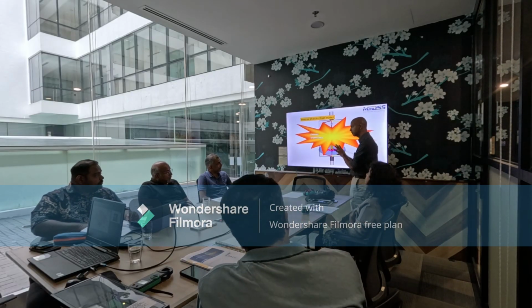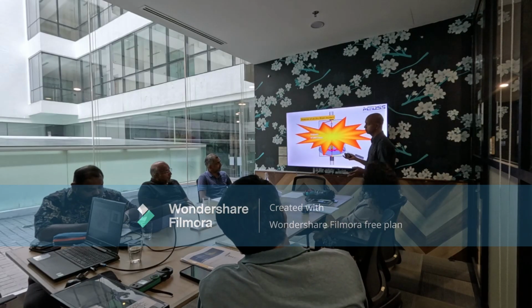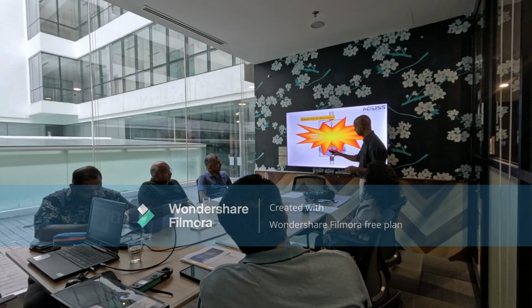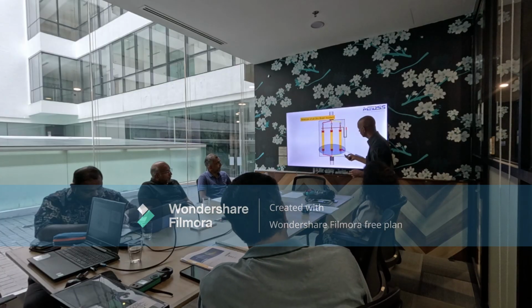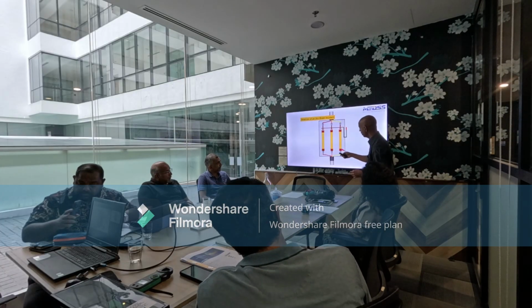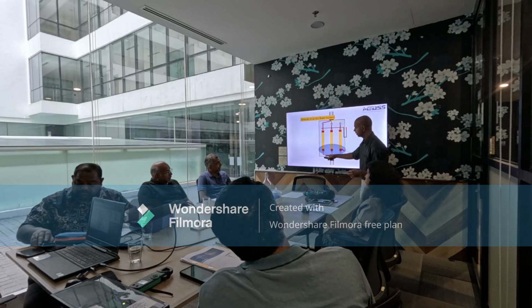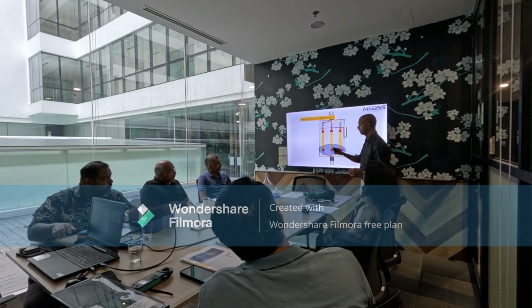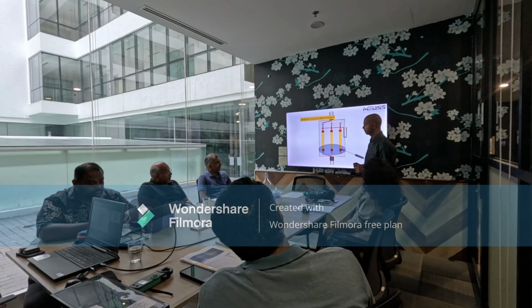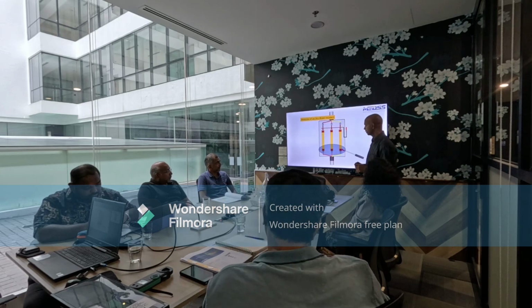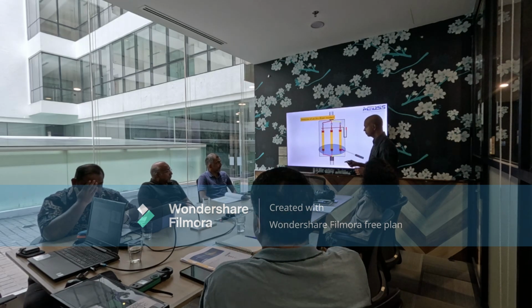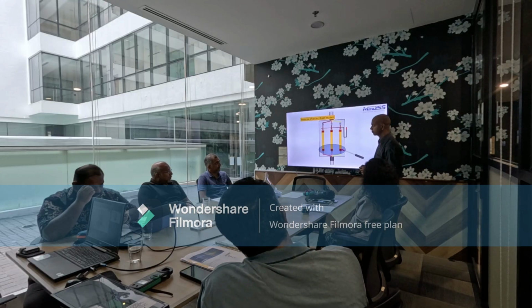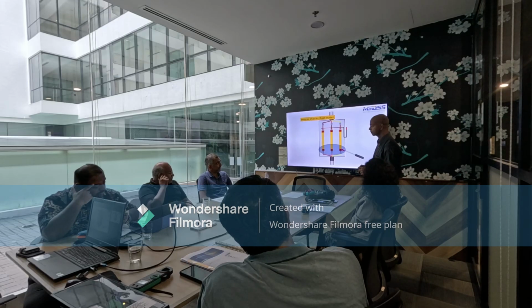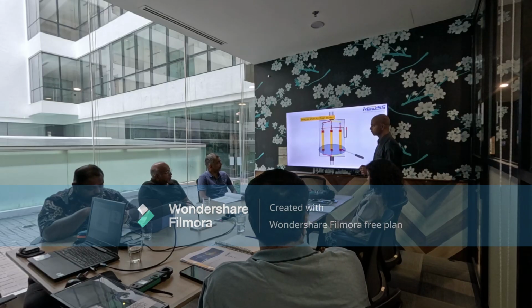Sometimes when things fail, we've seen it start off as a phase-to-earth fault. How does it extend to become phase-to-phase across other phases? That's my question. Any idea? When insulation fails, at first you probably get an intermittent fault with a ground fault. But if the insulation degrades further and gets severe, it tends to develop into a phase-to-phase short.